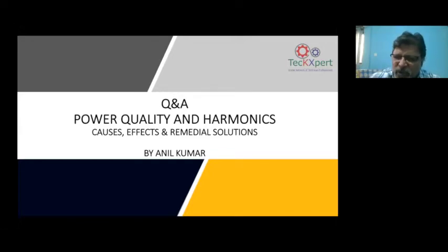So the answer to such problems, I would ideally say, is an active harmonic filter. The active harmonic filter can be selected to compensate the leading and lagging power factor on a real-time basis. When I say real-time basis, that means cycle to cycle, it looks at when the leading is taking place in a cycle, when the lagging is taking place in a cycle, and every cycle it injects leading or lagging reactive energy and keeps the power factor near unity all the time. So the answer to the question is to go in for an active harmonic filter with the option to give leading and lagging reactive energy along with harmonic mitigation.